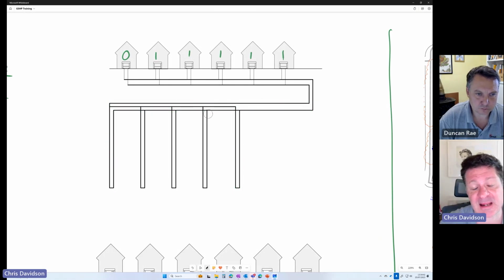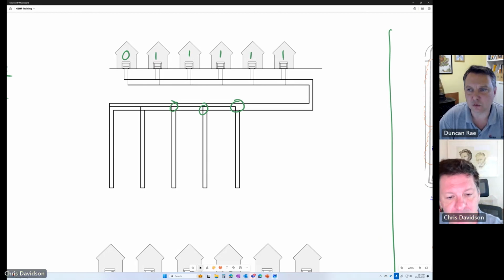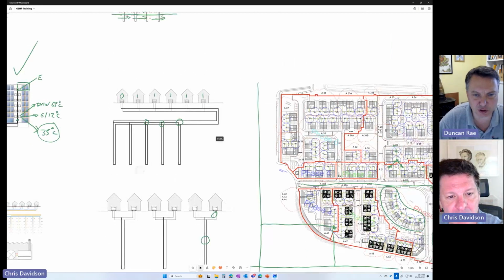Downside of the reverse return header is, of course, you don't have any valving connecting each borehole. So if you were to, in a very unlikely event, lose a borehole, then you'd have to dig up that borehole header to isolate it or replace it. That's interesting. How often do you lose boreholes?